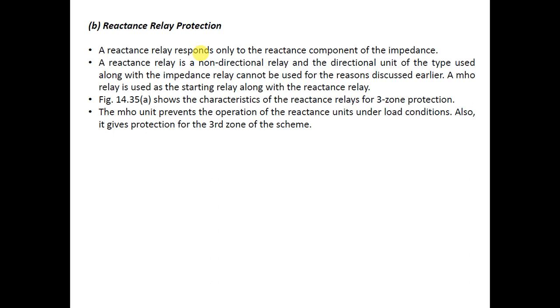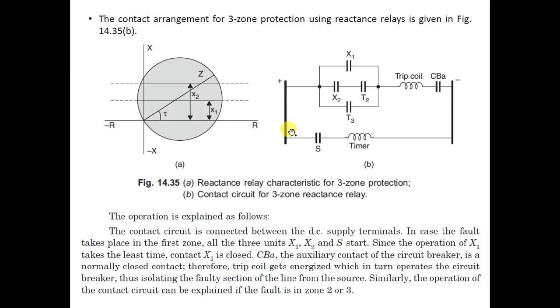Next is the reactance relay. A reactance relay responds only to the reactance component of the impedance. It is a non-directional relay, and the directional unit used along with the impedance relay cannot be used with it for reasons discussed earlier. So a mho relay is used as the starting relay along with the reactance relay. The mho relay's job is to prevent the operation of the reactance unit under load conditions and also to provide protection for the third zone of the scheme.